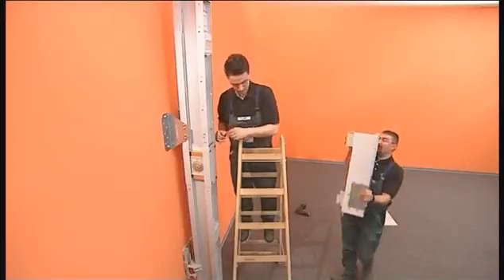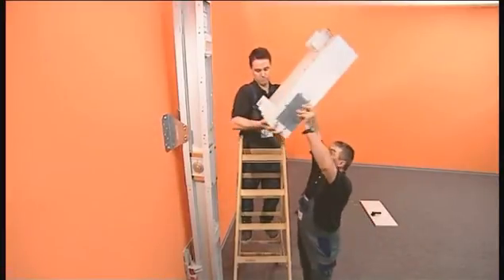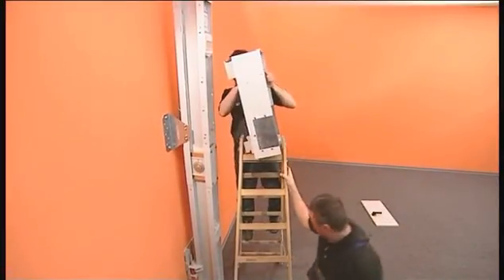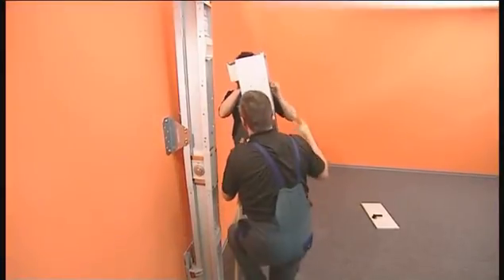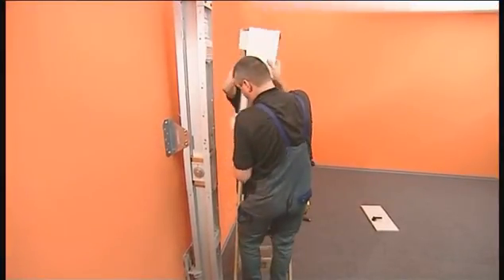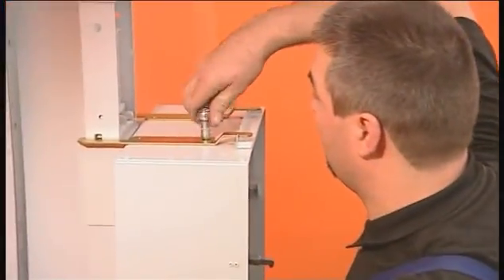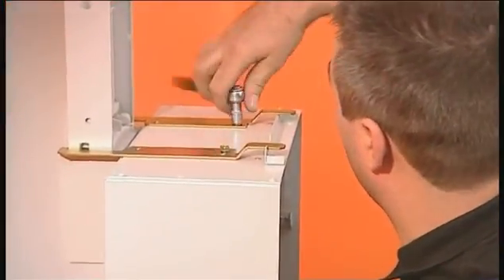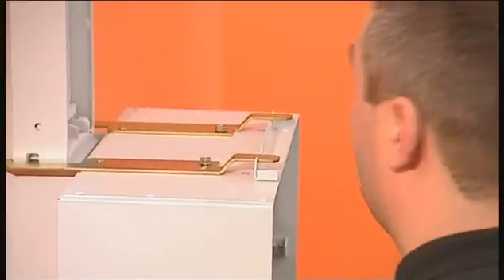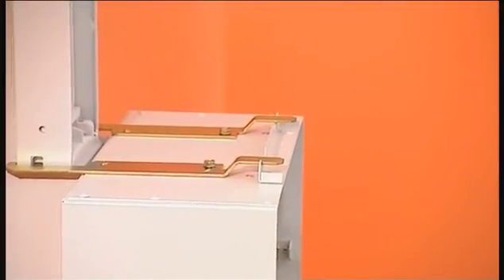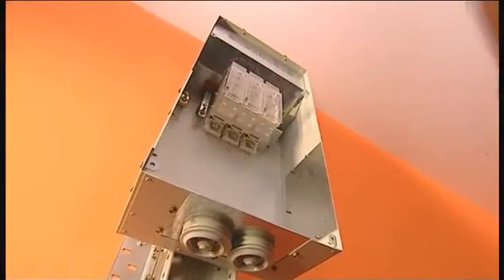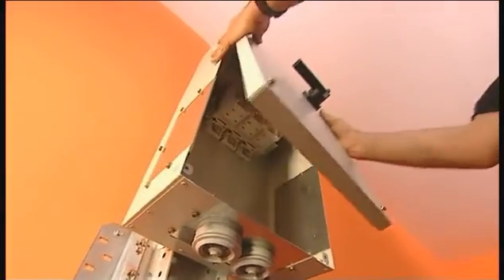The tap-off unit can now be mounted on the bus bar trunking unit by simply swiveling it. The tap-off unit is secured by closing the locking brackets and is now prepared for the connection of loads.